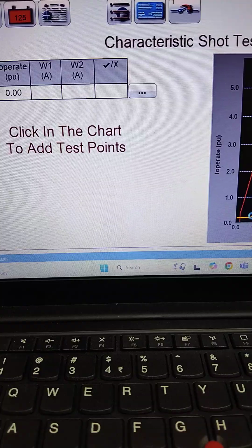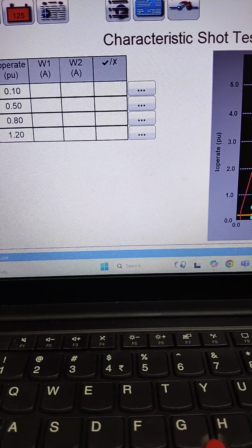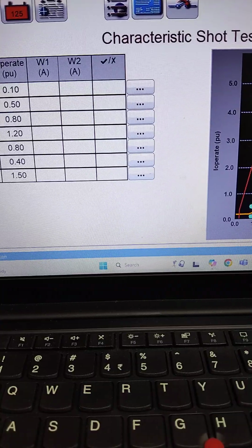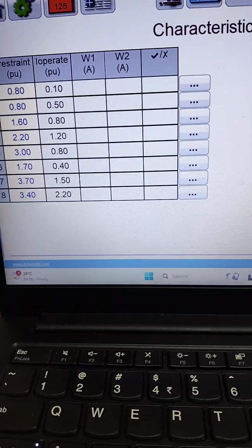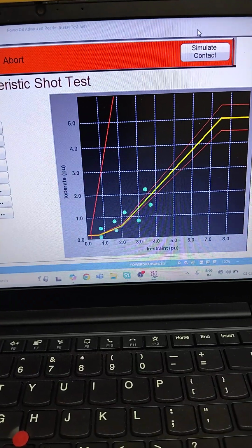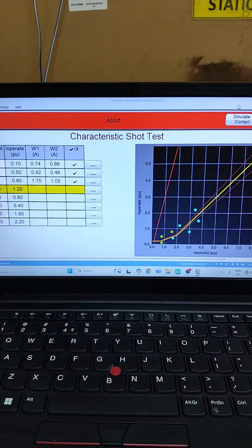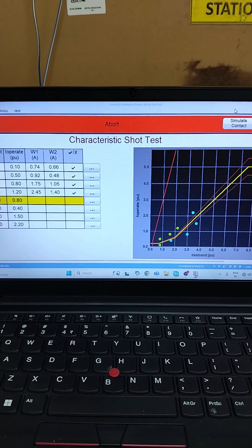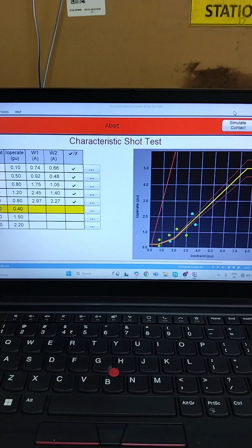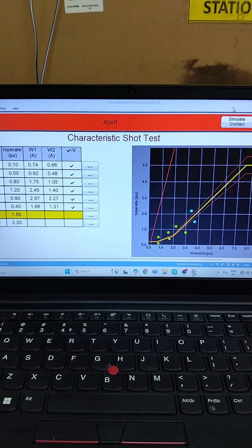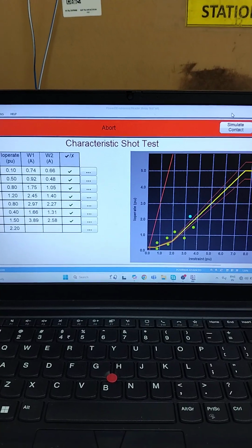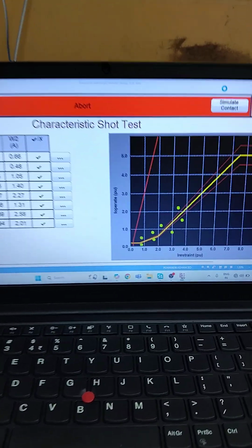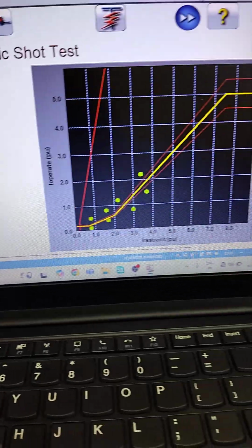In this you need to add shots in your restraint zone and trip zone, and for the restraint zone the relay should not trip, and for the trip zone it should trip. So you can check here again. So here no tripping, so it's passed. The other shot is in the trip zone, so trip. So on all the restraint zone shots we did not receive any trip, and on all the trip zone shots we received a trip. So this is the basic differential testing.